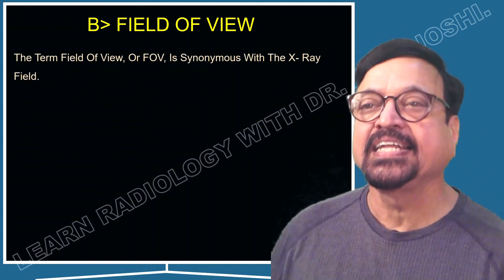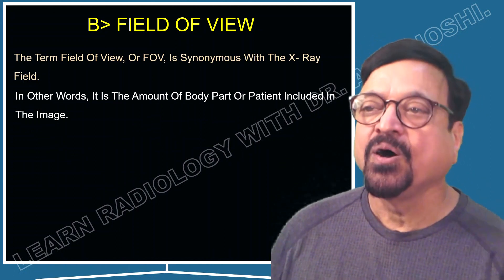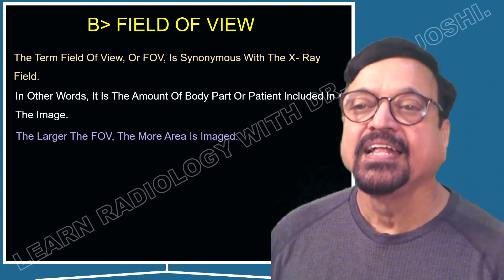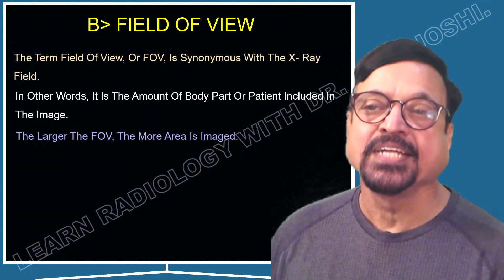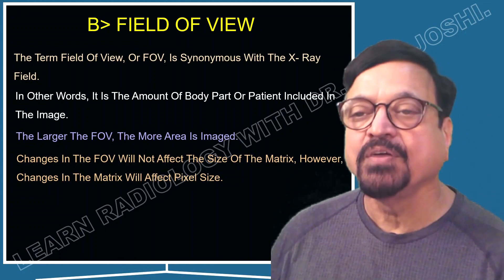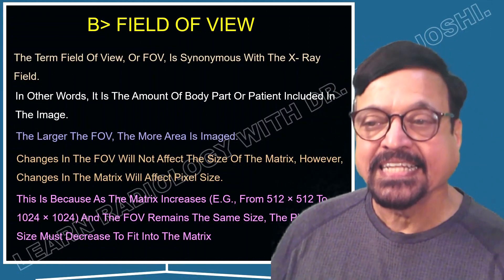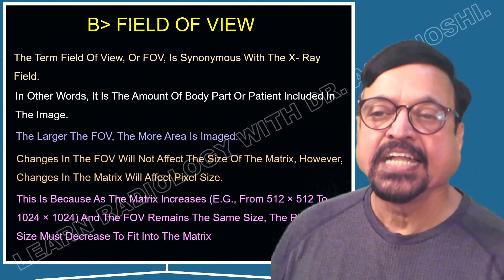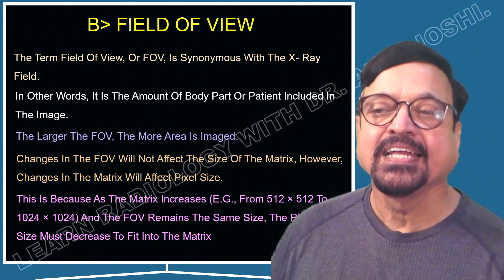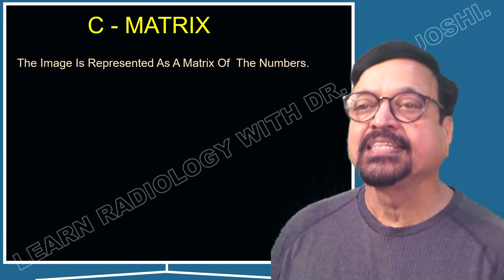The field of view (FOV) is synonymous with the X-ray field — in other words, it is the amount of the body part or patient included in the image. The larger the FOV, the more area is imaged. A change in FOV will not affect the size of the matrix; however, a change in matrix will affect the pixel size. For example, if the matrix increases from 512×512 to 1024×1024 and the FOV remains the same, the pixel size must decrease to fit within the matrix.